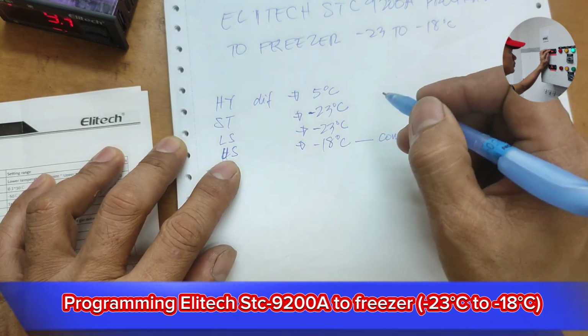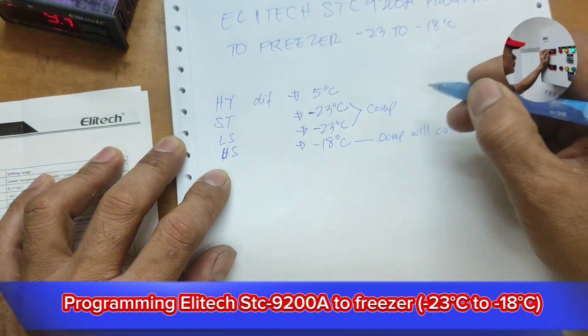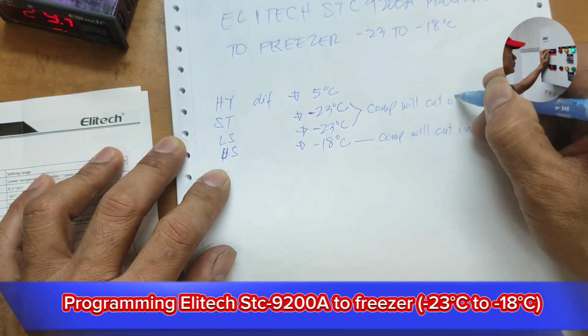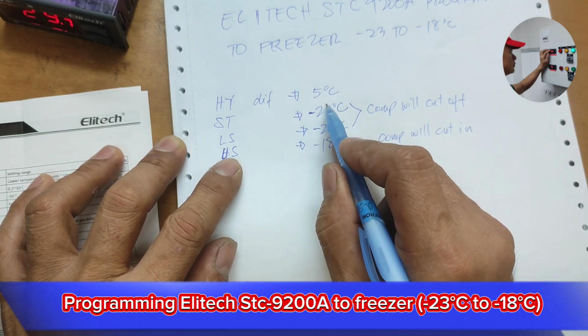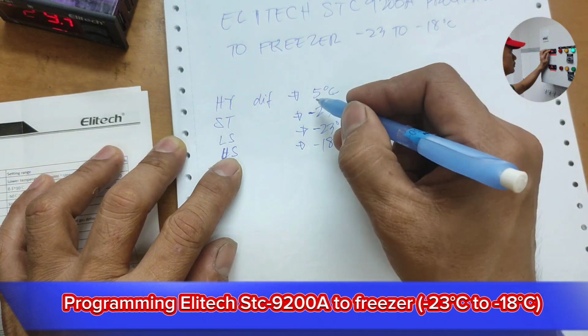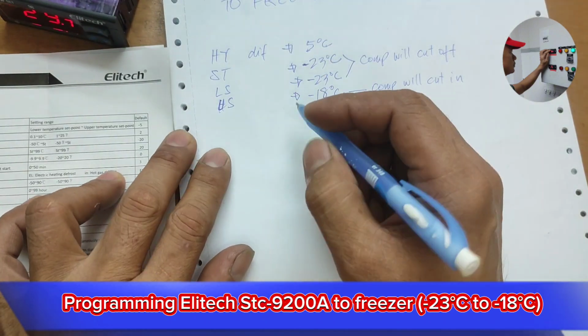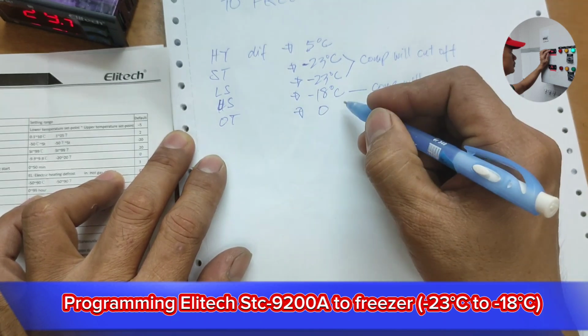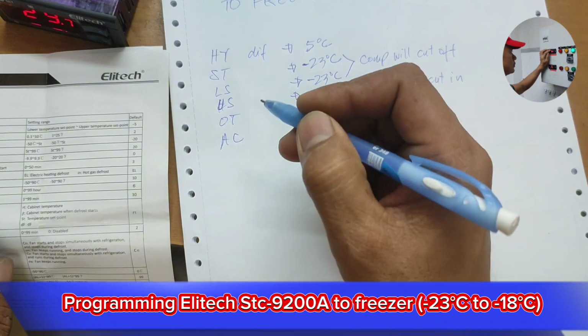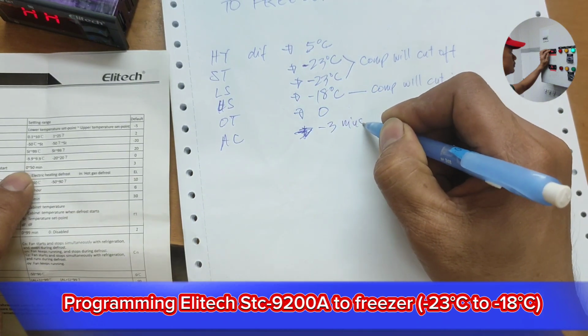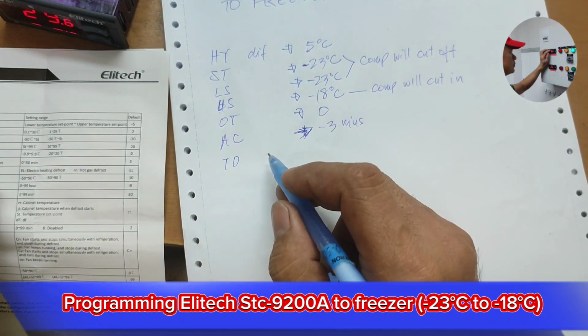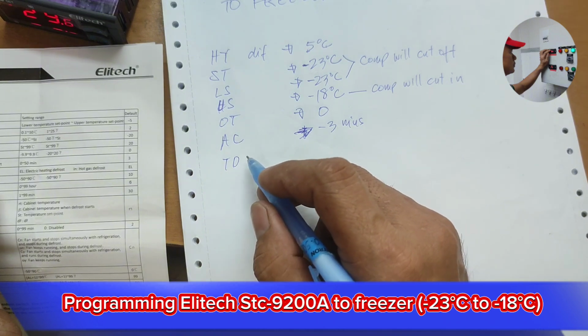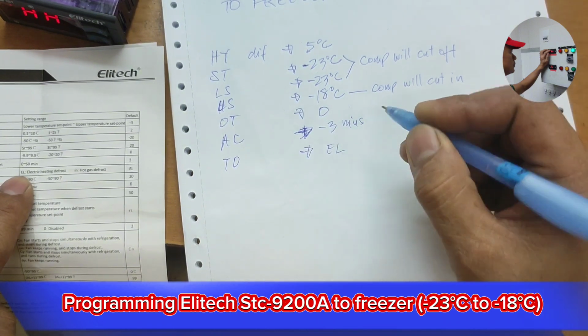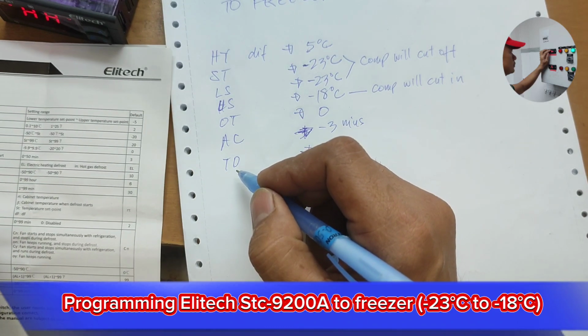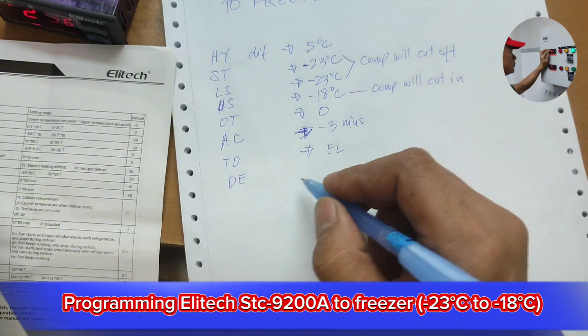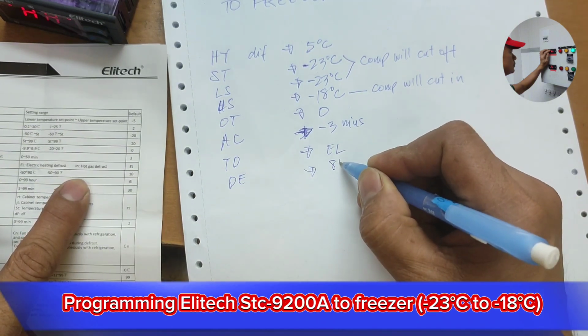Cut in. While in this temperature, the compressor will cut off, and we have negative 23 minus 18, which is 5 degrees Celsius, and this is our differential. After that, we have OT, just set it to 0. Then anti-short cycle, we set to 3 minutes. And we have TD, the defrost temperature. For the TD defrost mode, we select electrical, because we are in a freezer. After TD, we got DE, the defrost stop temperature, and we set it to 8 degrees Celsius.